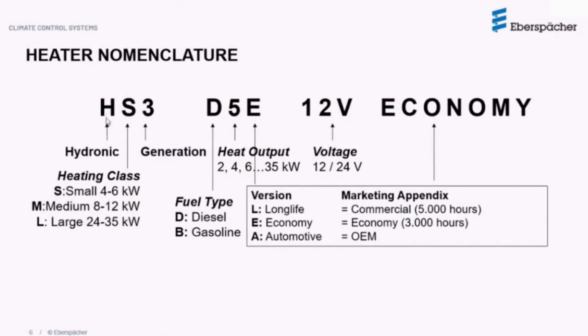H will stand for Hydronic, and the next part will identify the sizing or heater class, or size of the heater. So we have small, medium, and large classes. If the heating output is anywhere between 4 to 6 kilowatts, it will be designated as a small heater. Between 8 to 12, it's a medium heater, and anywhere from 24 to 35 would be a large heater.